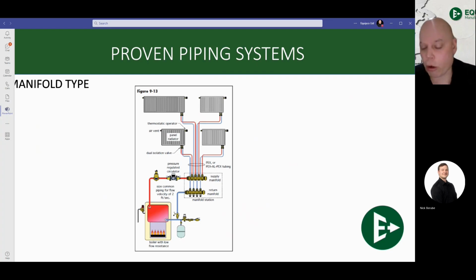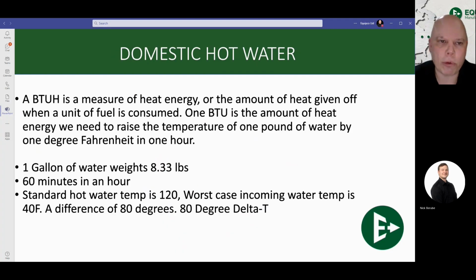Without getting onto a tangent, they are cost effective, easy to install, produce a ton of heat, and can be extremely beautiful. I don't know if you folks have ever seen the Jaga rads, J-A-G-A. Go check that stuff out. They're a lot more versatile and simple of a system where they don't require 10,000 feet of pipe inside of a system. Maybe now you're only talking about half a dozen rads to do the exact same job. But my point being here, you can use manifolds to feed systems like this, where you're feeding different panel rads or different heat emitters. Don't be afraid to use your manifolds a little bit outside the box, other than just in in-floor systems. So that's essentially what I have here for your hydronic training today.